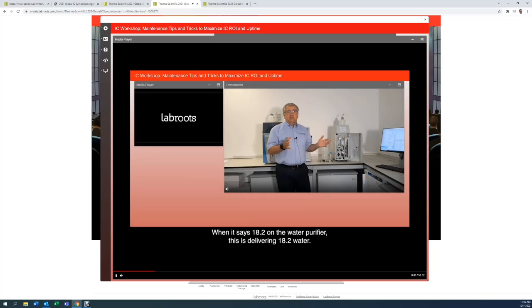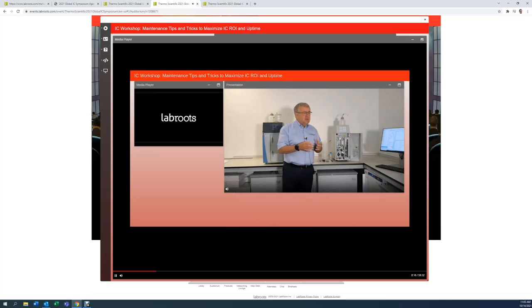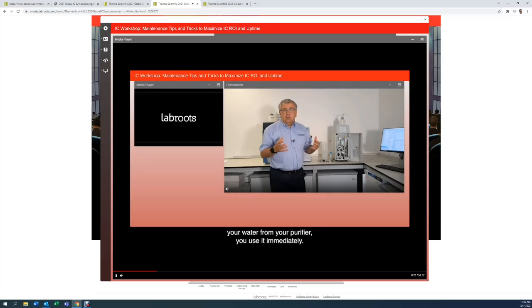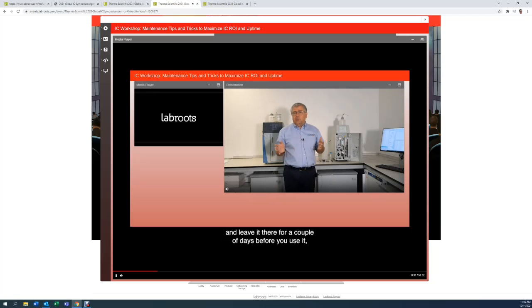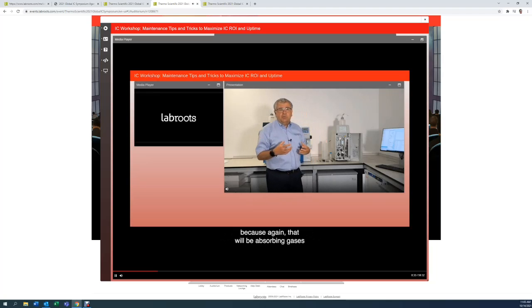When it says 18.2 on the water purifier, it is delivering 18.2 water. But as soon as that water is manufactured, it will start absorbing carbon dioxide, and the quality of the water quite quickly deteriorates. So it is, again, quite important that when you are using your water from your purifier, you use it immediately. You don't put it into a carboy at the end of the laboratory bench and leave it there for a couple of days before you use it, because again, that will be absorbing gases from the environment and diminishing the quality of the water.